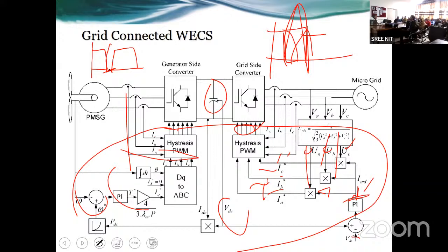You are getting? The upper device is coming down, the upper pulse is coming down, and the lower device starts turning on. So during that superimposed, overlap period, the power will be there across the switch, which will appear in the form of switching losses. So if you are looking for soft switching, you must give sufficient delay. Dual active bridge, DAB, have you heard about it?